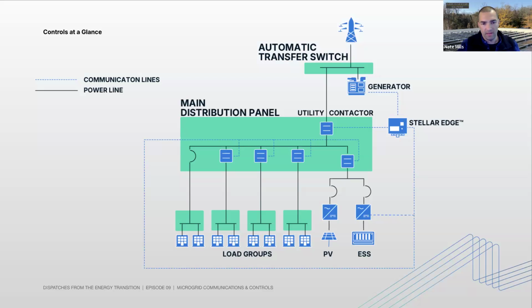Some of those loads may or may not be shed, just depending on what we decide to do with the system. The battery is in grid forming, but if the production from solar can't match what the loads are requiring, the battery will drain down, and when it gets to a sufficiently low state of charge, the Stellar Edge will send a signal to the generator to start. The generator will start. The utility contactor there will see that there's stable power on the utility side of it. It doesn't really care where that power is coming from. And then we can sync across that contactor, close it, and allow the battery to charge.